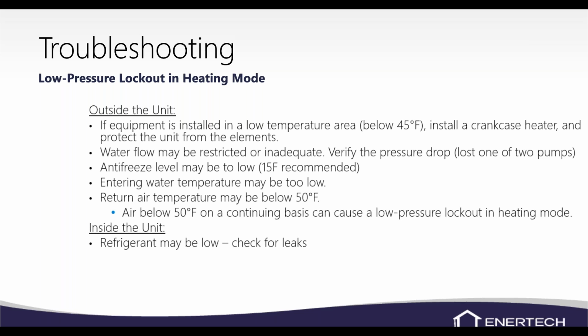You could have low return air temperature. If that's the case, you may want to run your backup heat, bring up the space temperature in the building, and then turn your geo back on. If it's below 50, we could run the risk of getting into that low pressure lockout in heating mode. Usually about 60 degrees or so is where we want to do startup and get the building up to temperature.